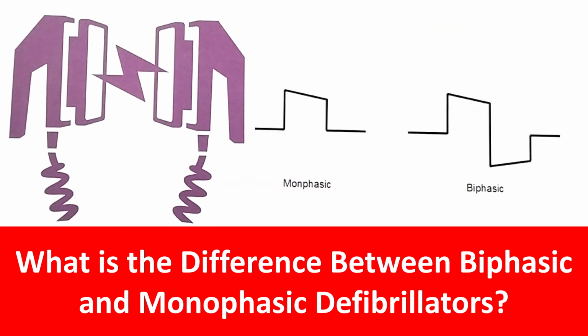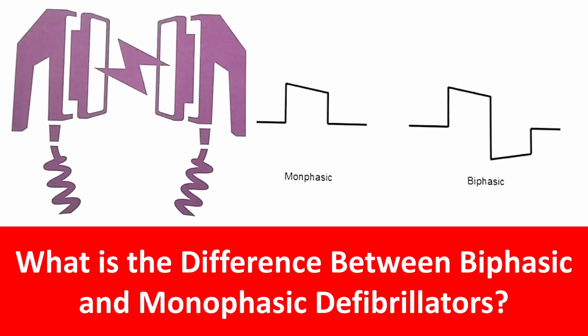We'll know a little bit about the physics of the defibrillators, or rather the electronic side. The voltage usually given in a biphasic defibrillator is an enormous 2500 volts direct current, DC. Whenever the defibrillator is used on AC, it is stepped down initially to the usual battery voltage to charge the battery. Often the defibrillators work much better on the battery. Direct current from the battery is converted to a high voltage by a voltage multiplier circuit, and it is stored in a high value capacitor for a short period when you are activating the defibrillator. That's why you can see charging in the defibrillator.